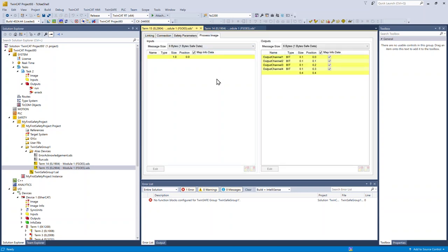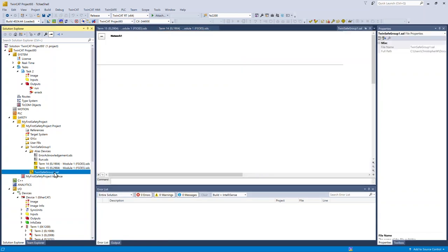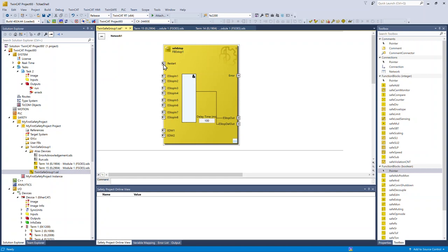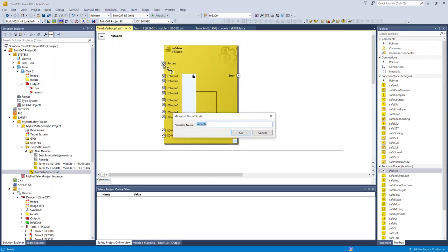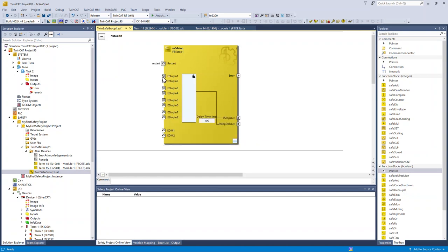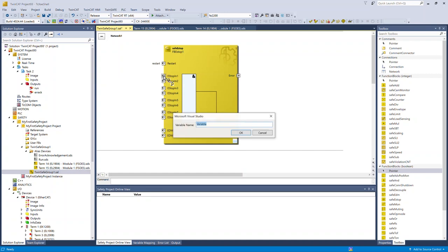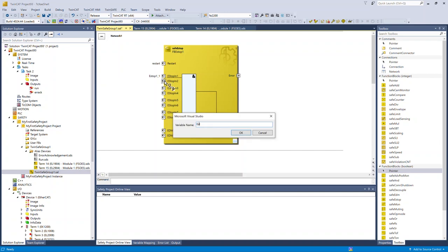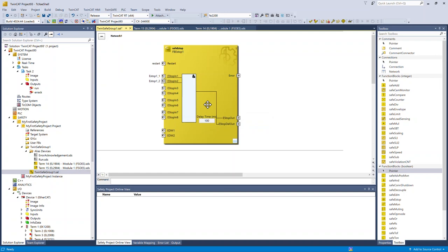Now I'm going to open up the safety application language worksheet. It's the programming environment. Under toolbox, I'm going to drop in a simple e-stop. I'm going to create variables for restart. I'm going to imagine that my e-stop has two contacts. So e-stop one underscore one and e-stop one underscore two. And I'm going to give my safety function an output.